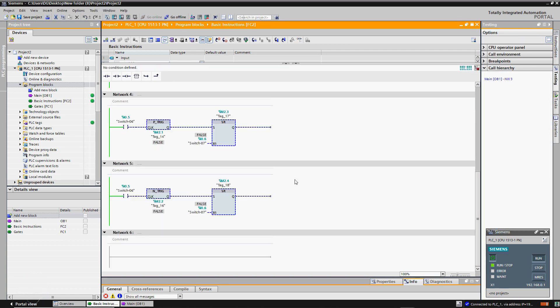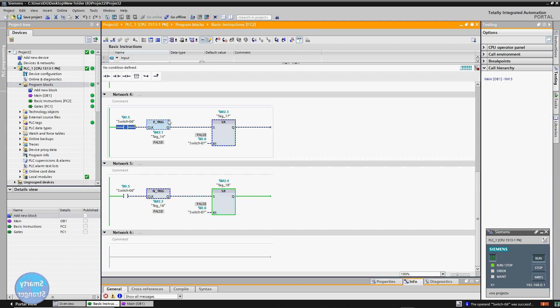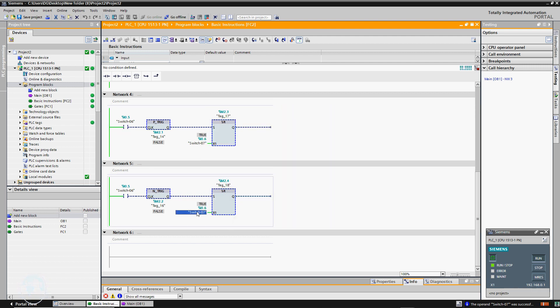Run the PLC simulator and turn monitoring on. The input signal is low initially. When we press the button, the P-trig instruction detects the rising edge of the signal and triggers the SR flip-flop, whose output Q becomes high. To check the falling edge, we use the same input signal in both networks. When we release the button, the N-trig instruction receives the falling edge and sends a high signal to the second flip-flop, whose output Q becomes energized. We then reset that flip-flop by pressing its R pin. One flip-flop detects the rising edge and the other detects the falling edge.